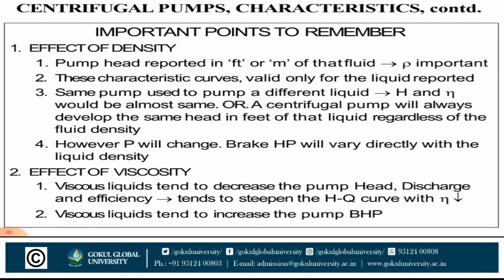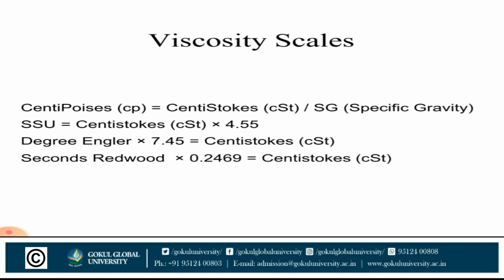Effect of viscosity: viscous liquid tends to decrease the pump head, discharge and efficiency, and second, viscous fluid tends to increase the pump power. Viscosity scale.